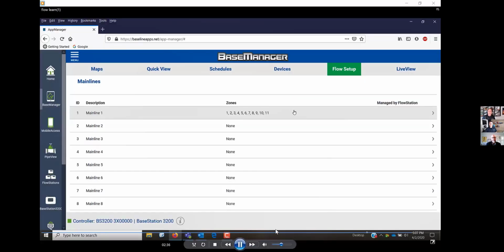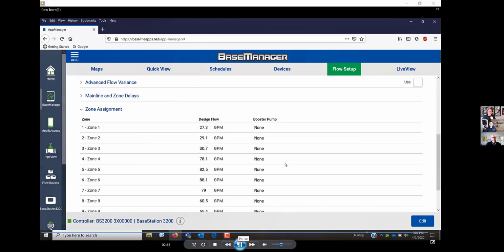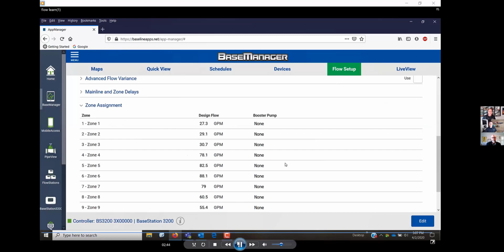Okay. So what I wanted to show you here was, once we've learned flow, oh, I went too far. Once we've learned flow, I can go into my mainline settings and zone assignments. Now I can see the real flows that have been populated, right? So once I see these flows, then I know that I've actually learned the flow, and then the controller has those flows to use going forward.